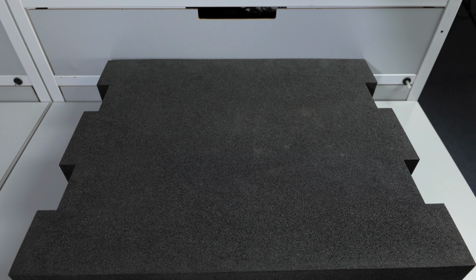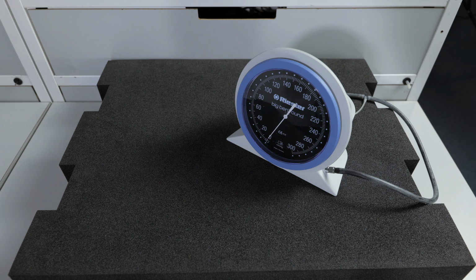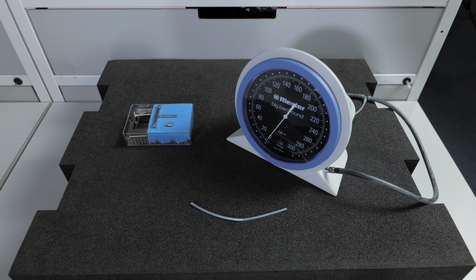The accessories that are included, used for maintaining your equipment, include a Big Ben manometer, a calibration shunt, a force calibration kit used to calibrate the force transducer, clear silicone-based grease which will protect any openings near the chamber, brown petroleum-based grease for the micrometers, a pack of replacement cover glass, and extra screws.